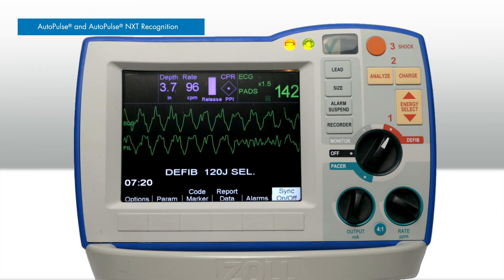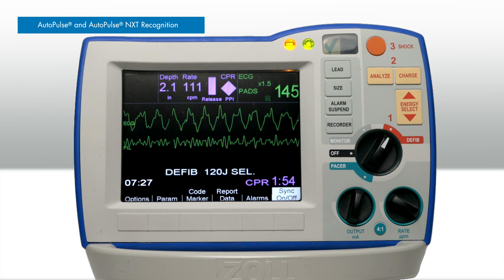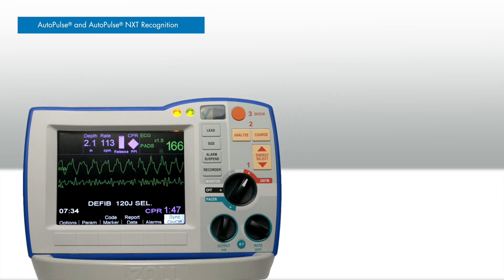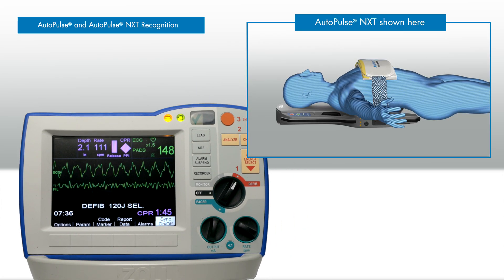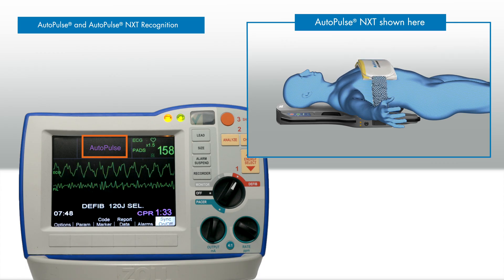The new AutoPulse recognition algorithm automatically detects AutoPulse or AutoPulse NXT resuscitation system compressions when using the R-Series monitor defibrillator with authorized Zoll CPR electrodes. When the R-Series ALS or R-Series Plus detects the AutoPulse signature compression, the on-screen CPR feedback adjusts to display AutoPulse in the CPR dashboard, and audio prompts for the depth of compression are suppressed.